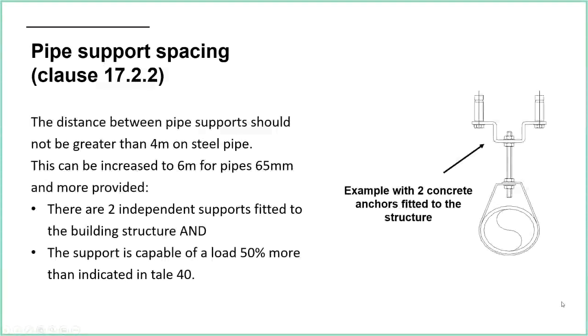Moving on to talk about spacing. So again, in general, we shouldn't have more than 4 meters between some kind of support for the pipework. However, this can be increased to 6 meters for larger pipes, so 65 millimeter pipes and larger, provided there are 2 independent supports and the support is capable of 50% more than what is listed in Table 40. So there's an example there on the right-hand side.